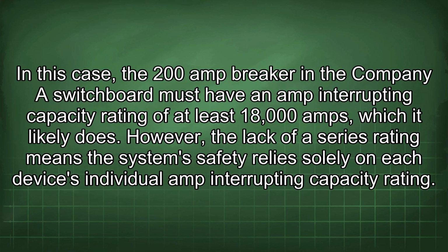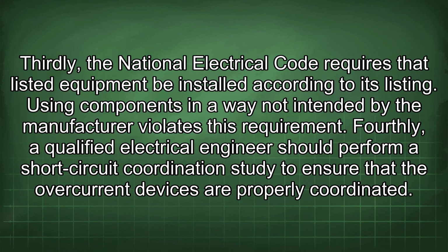In this case, the 200 amp breaker in the Company A switchboard must have an amp interrupting capacity rating of at least 18,000 amps, which it likely does. However, the lack of a series rating means the system's safety relies solely on each device's individual amp interrupting capacity rating. Thirdly, the National Electrical Code requires that listed equipment be installed according to its listing. Using components in a way not intended by the manufacturer violates this requirement.